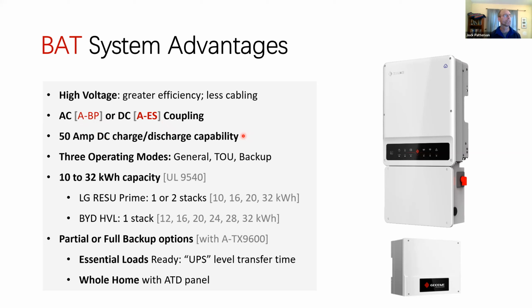The 50 amp charge discharge, you're not always doing 50 amps. You're capable of doing that, right? If your inverter is rated for less, you're not necessarily going to be doing that. The point is that the inverter is able to handle up to 50 amps. That means that if the battery is capable of doing it, there's no bottleneck. Often the bottleneck in an ESS, an energy storage system, is between the battery and the inverter. If you pair it with a battery that is designed to be compatible with it, you'll get the high power throughput and the inverter will be able to handle it. So that's what we paired with. More on that a little bit later.